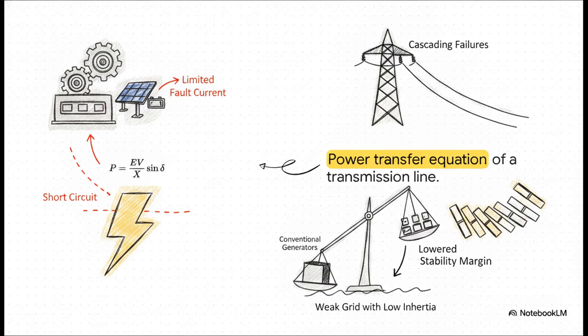And it's not just frequency we have to worry about, it's also transient stability. The math you're looking at here models power transfer and the system's ability to remain synchronized after a large disturbance, like a short circuit. Because inverter-based renewables provide really limited fault current compared to those old conventional generators, our transient stability margin is drastically lowered. To put it simply, lightweight renewables just lack the raw brute force to punch through a disturbance. And that means a sudden fault is way more likely to trigger cascading failures across the whole entire system. That delicate balance, it's completely lost.